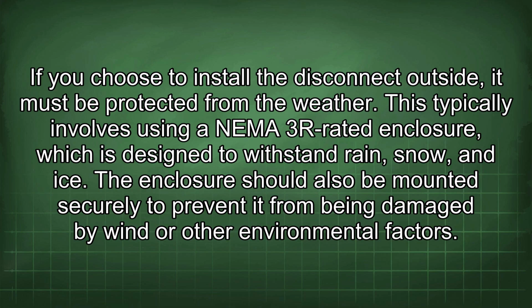If you choose to install the disconnect outside, it must be protected from the weather. This typically involves using an NEMA 3R-rated enclosure, which is designed to withstand rain, snow, and ice. The enclosure should also be mounted securely to prevent it from being damaged by wind or other environmental factors.